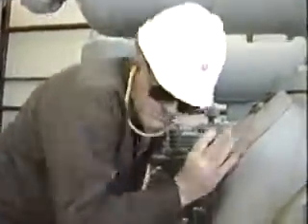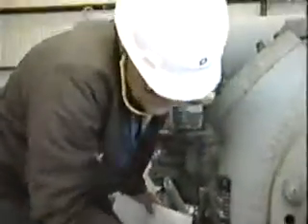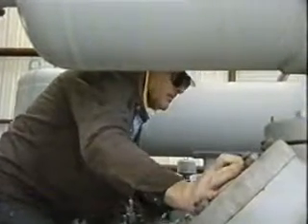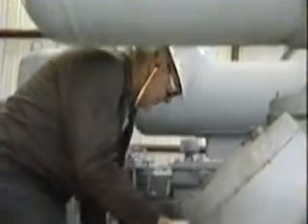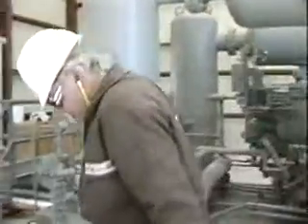All reciprocating compressors require troubleshooting at one time or another. Control panels may be helpful in identifying the source of a problem, but many symptoms can also be detected by sound and visual clues. Since problems can arise in either the compressor or prime mover, being visually aware of operating changes and alert to noises out of the normal range can be one of your best ways to find those problems.